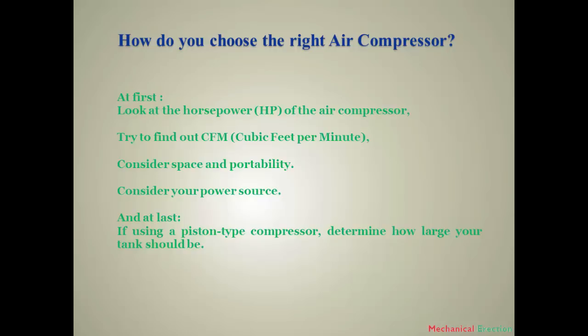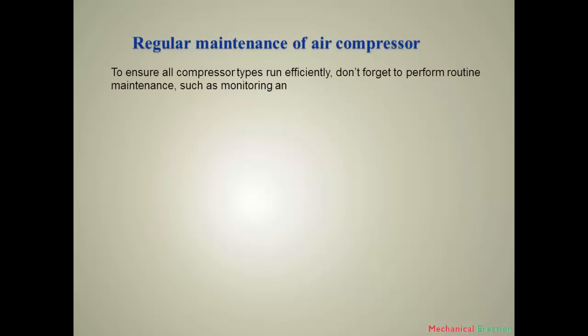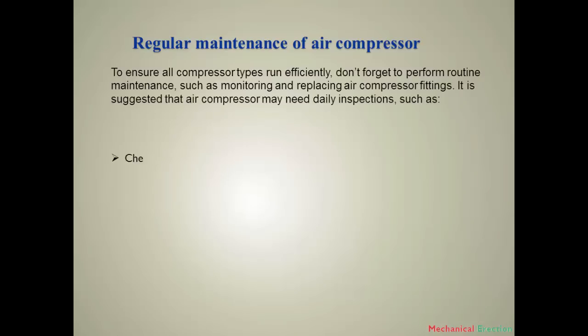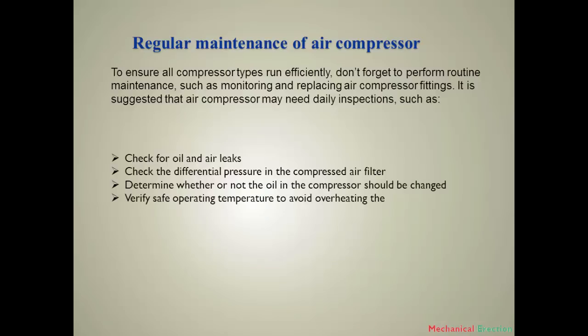Now, you have to know the regular maintenance of an air compressor. To ensure all compressor types run efficiently, don't forget to perform routine maintenance such as monitoring and replacing air compressor fittings. It is suggested that air compressors need daily inspections: check for oil and air leaks; check the differential pressure of the air filter; verify safe operating temperature to avoid overheating; and determine whether the oil in the compressor should be changed. These are the regular checklists you should follow and check regularly.